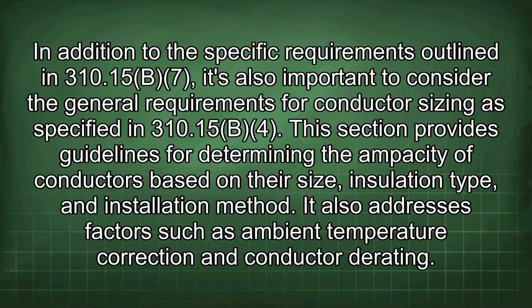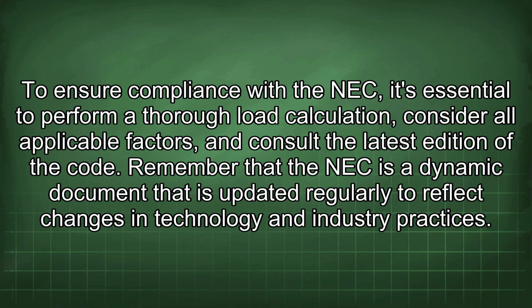In addition to the specific requirements outlined in 310.15(B)(7), it's also important to consider the general requirements for conductor sizing as specified in 310.15(B)(4). This section provides guidelines for determining the ampacity of conductors based on their size, insulation type, and installation method. It also addresses factors such as ambient temperature correction and conductor derating. To ensure compliance with the NEC, it is essential to perform a thorough load calculation, consider all applicable factors, and consult the latest edition of the code.